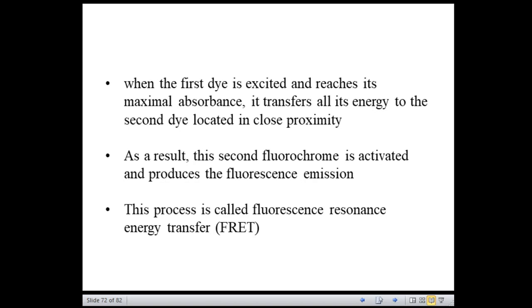This process is called fluorescence resonance energy transfer, abbreviated as FRET. This is a good way to obtain a higher Stokes shift that increases the number of colors analyzed from a single laser wavelength. That is the refinement in the technology, so that FRET offers a higher Stokes shift that increases the number of colors analyzed from a single laser wavelength.